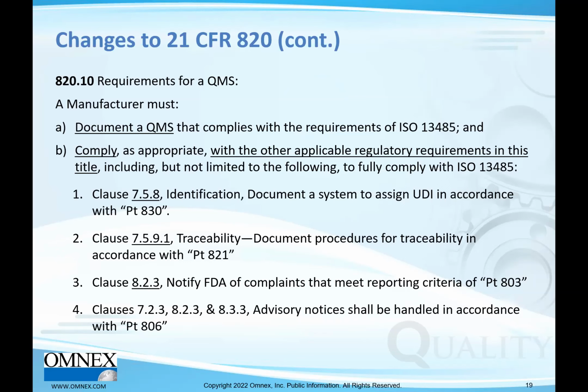Clause 823 is reporting to regulatory authorities. So notifying the FDA of complaints that meet the reporting criteria of Part 803. Again, not a part of 820. You have to go to 803 to find out what those reporting requirements are.